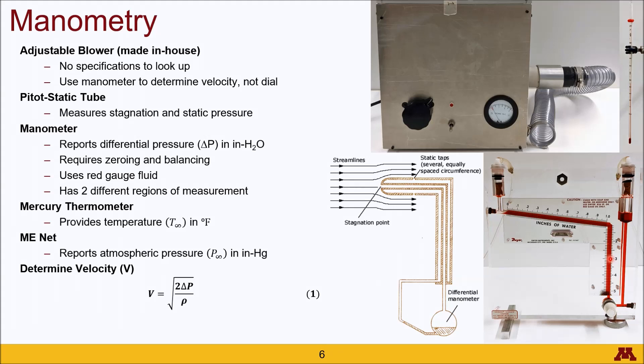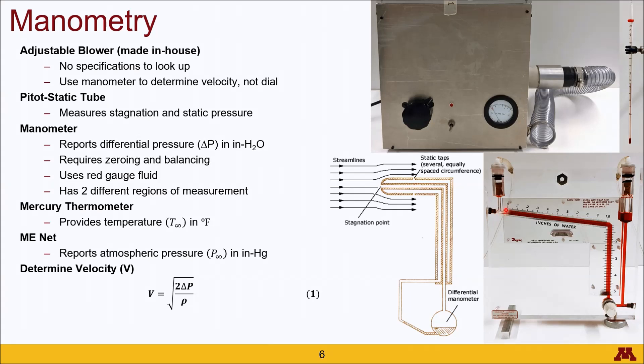To operate the manometer, first level it using the bubble level, which can be adjusted with the knob at the bottom right. The knob just above that is used for zeroing the manometer so that at zero velocity the right edge of the bubble is aligned with zero. Note that there are two different reading regions: an inclined manometer region with finer resolution, and a vertical region which allows larger increments but has poorer resolution comparatively.